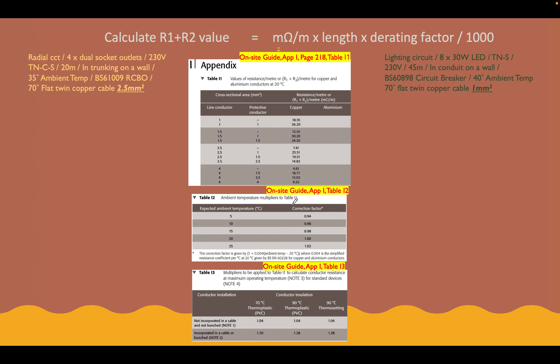The ambient temperature multipliers to add to Table I1 are our de-rating factor. For example, if our ambient temperature was 25 degrees for our circuit, our de-rating factor would be 1.02. The table at the bottom gives multipliers to be added to Table I1 to calculate conductor resistance at maximum operating temperature for standard devices. It's more important that we know our cable can work at maximum operating temperatures — the worst-case scenario, which is always what we consider in cable design. So we're going to use that bottom table to get our de-rating factor.